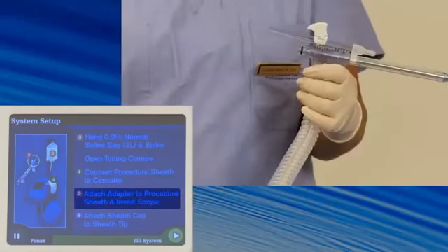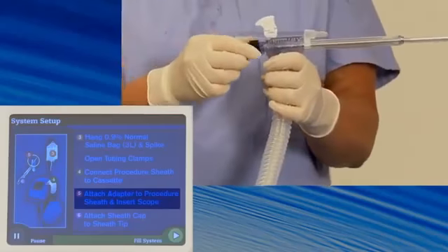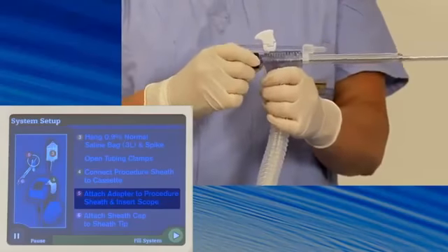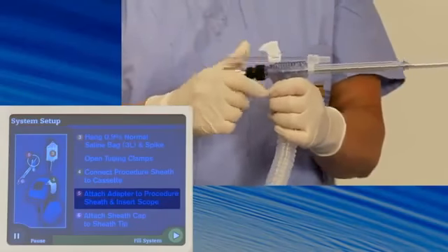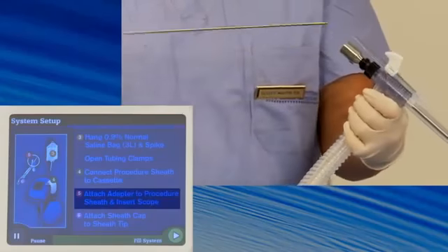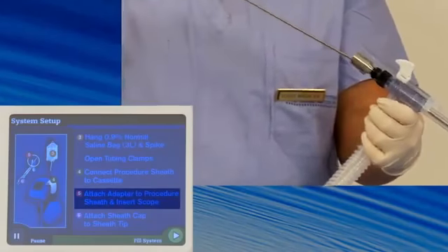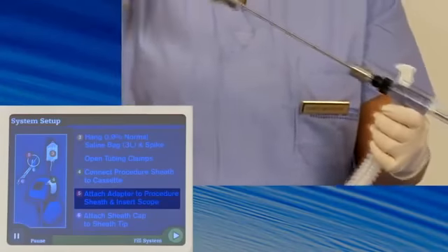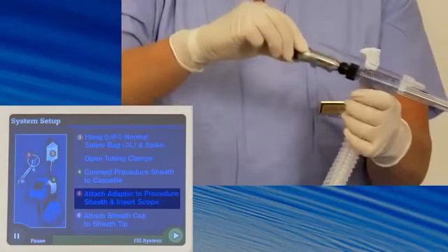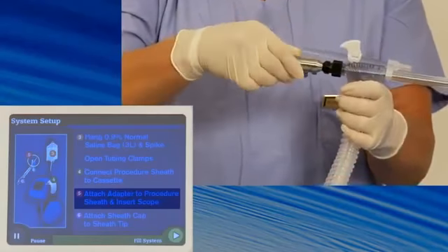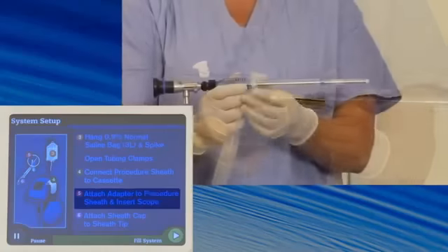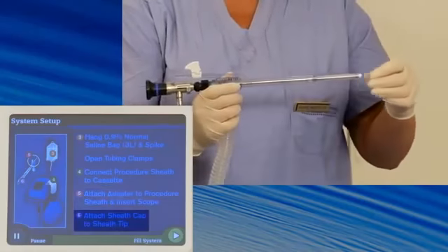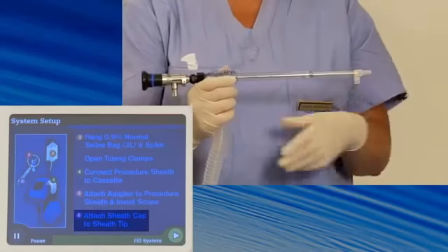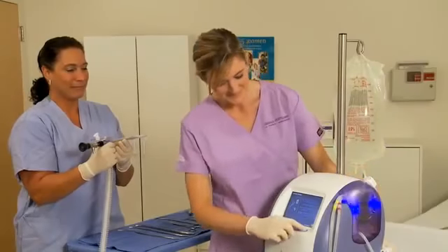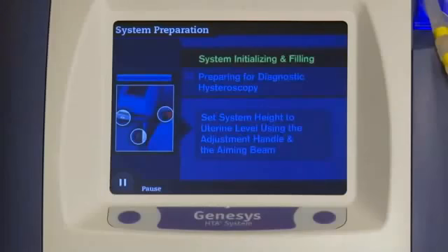Next, attach the scope adapter to the proximal end of the procedure sheath by pushing the adapter over the O-ring and screwing into place. Carefully guide the hysteroscope through the procedure sheath until it stops in the scope adapter. Then connect the hysteroscope to the adapter. Now attach the sheath cap to the tip of the procedure sheath and press the right console button. The system will now initialize and fill.